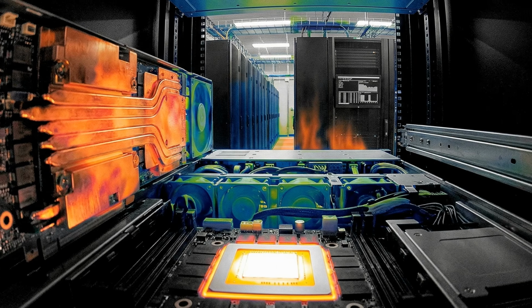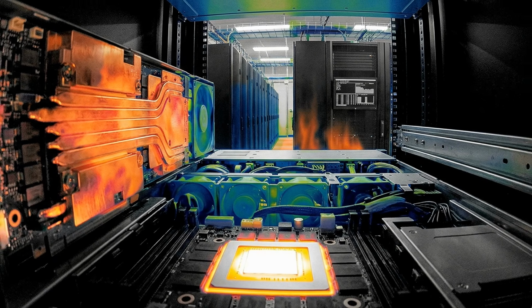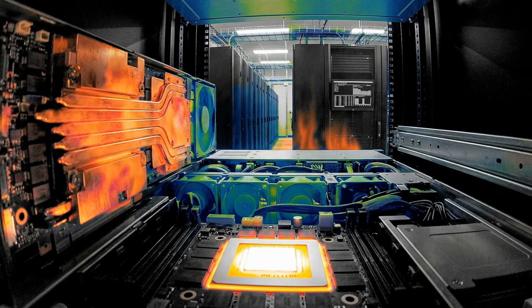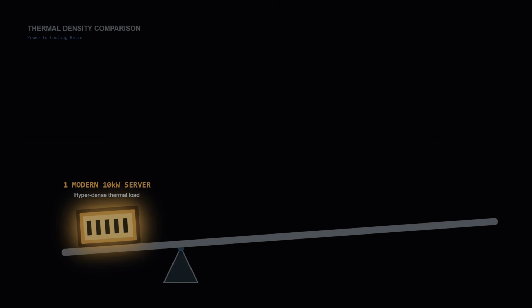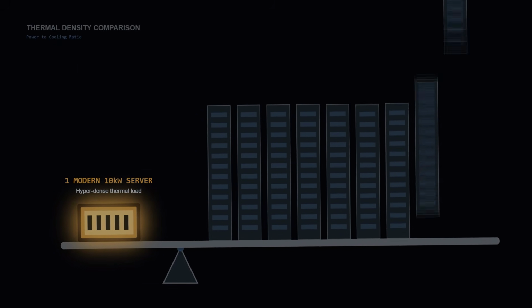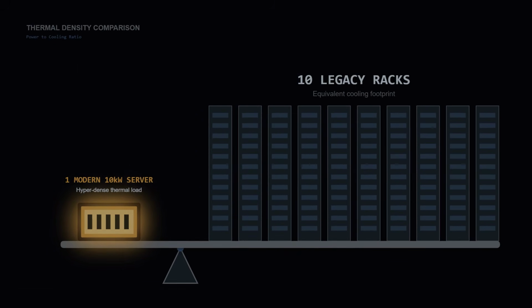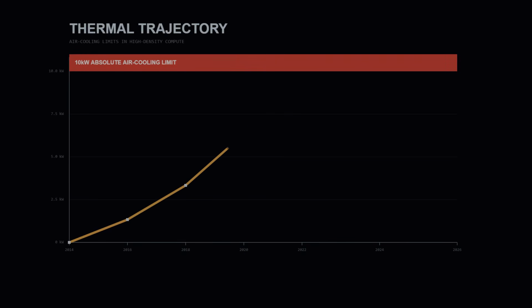But here we need to follow that heat out of the silicon and into the facility itself. Traditional data centers were built to cool racks that draw maybe 5 to 8 kilowatts for the entire cabinet. Now a single server demands more cooling capacity than an entire row of legacy hardware. This is the 10-kilowatt thermal wall.